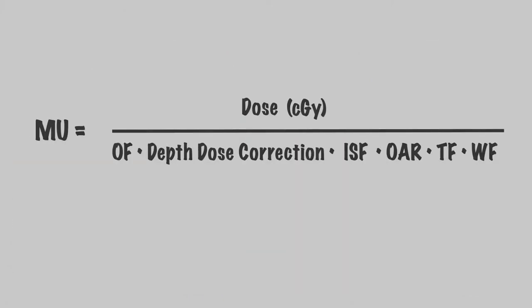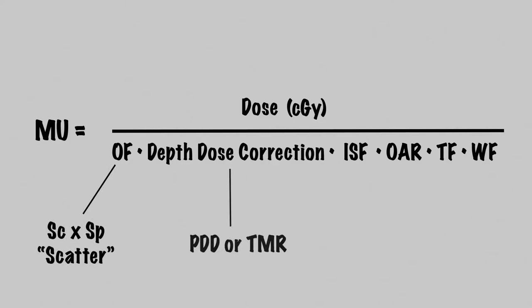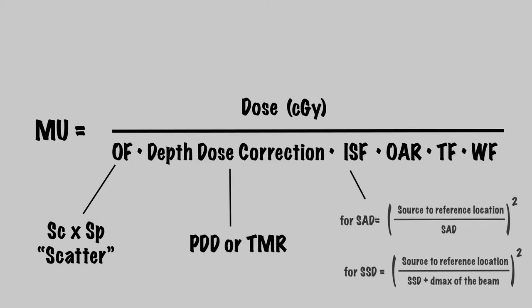With this knowledge, we can develop a formula. Each of the discussed modifiers impact the dose reaching our point or target of interest, so they go in the denominator of our formula. Therefore, our formula becomes dose in centigray divided by output factor, the depth dose correction, the inverse square factor, and any other modifiers such as off-axis ratio, tray factors, or wedges.